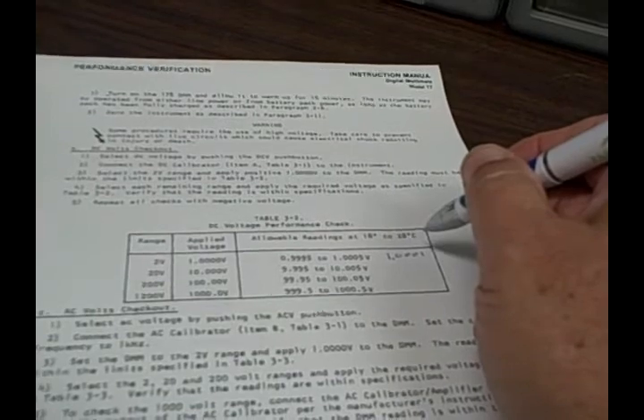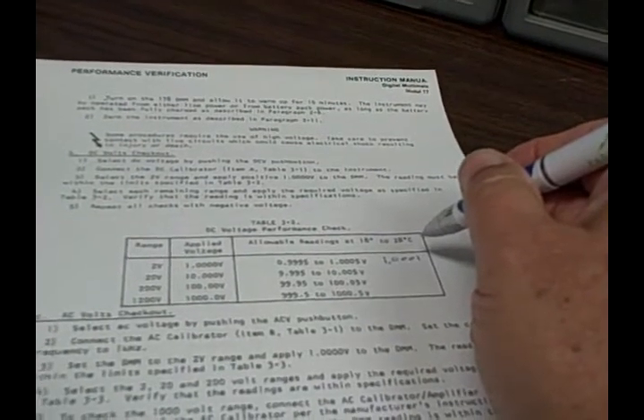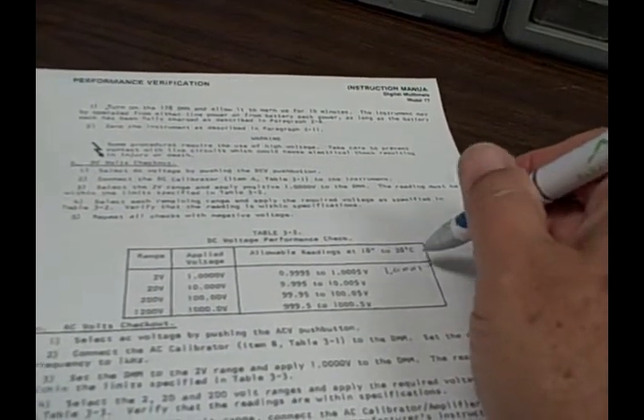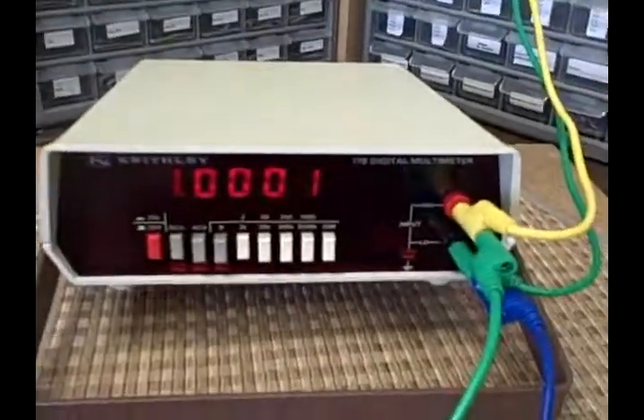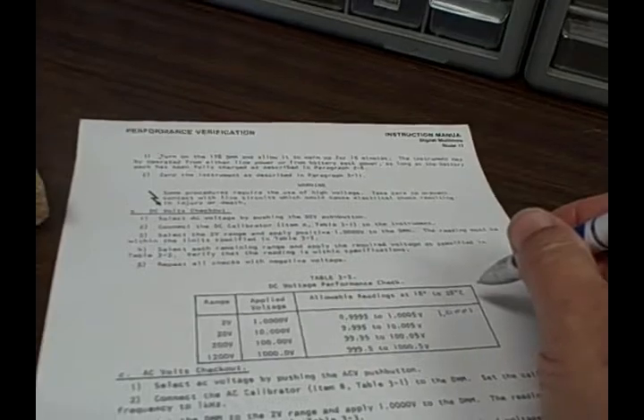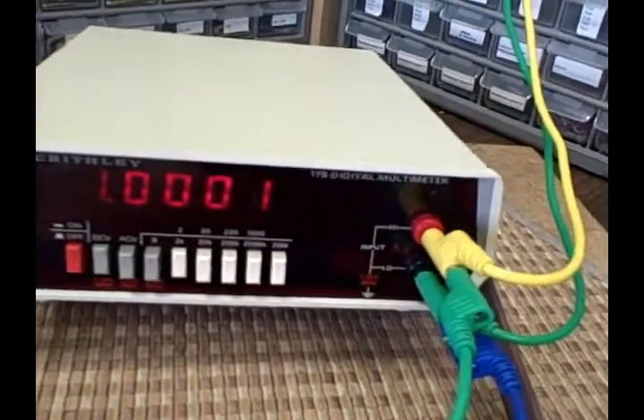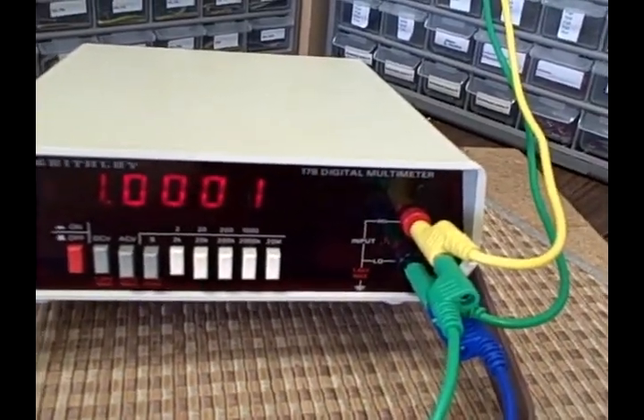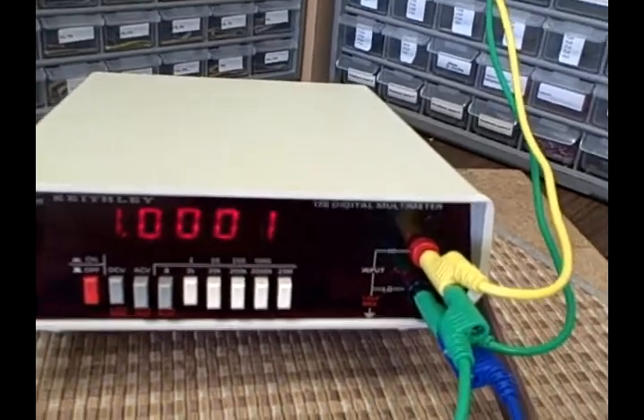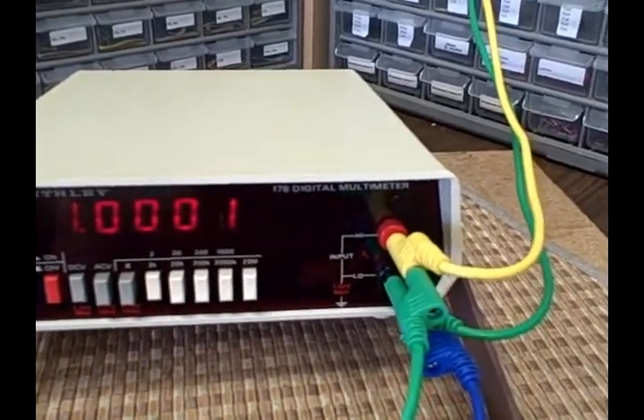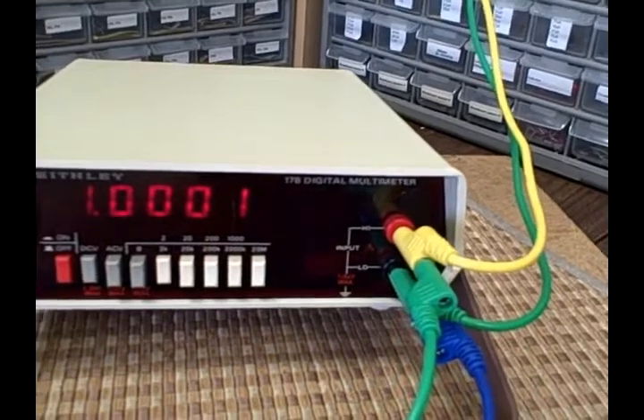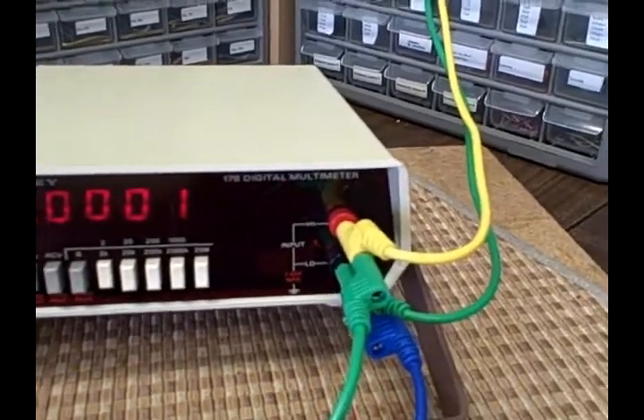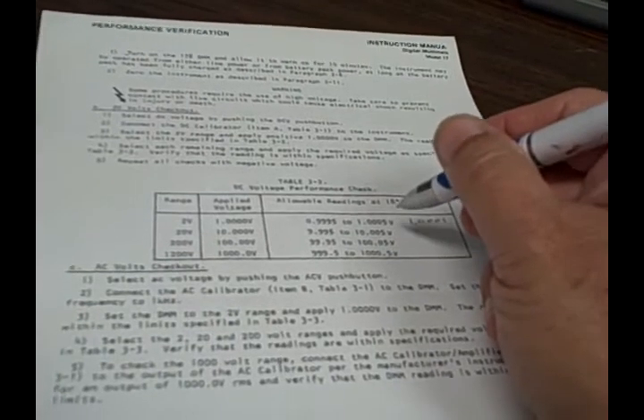We are 100 microvolts high in reading, and that seems to be a characteristic of this meter. As I go up the range closer to 2 volts, like at 1.9, the two meters match exactly. 1.9 volts is the calibration point for the unit. But we are better than 0.04% here.